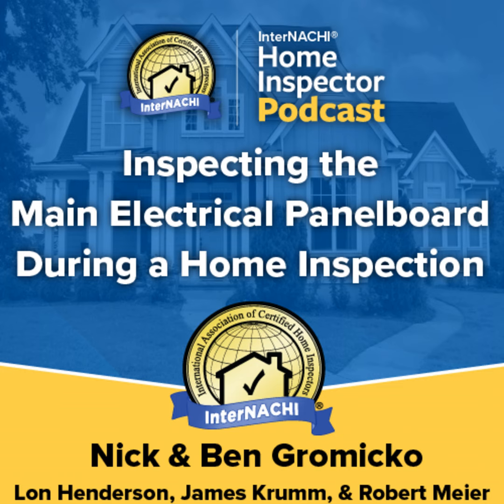For new construction, the main breaker or breakers is usually located in one panel board cabinet. The multiple service disconnecting means should be grouped together and marked. Most electric services will have a single main service disconnecting means located either outdoors on the load end of the meter or in an indoor panel board.